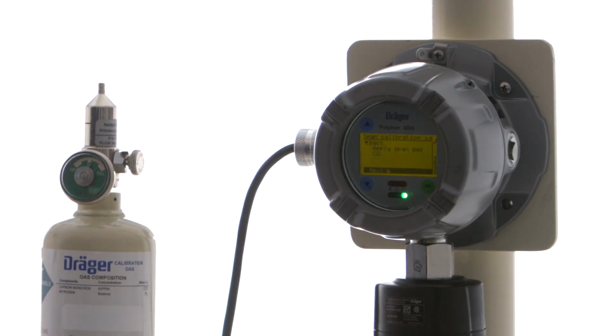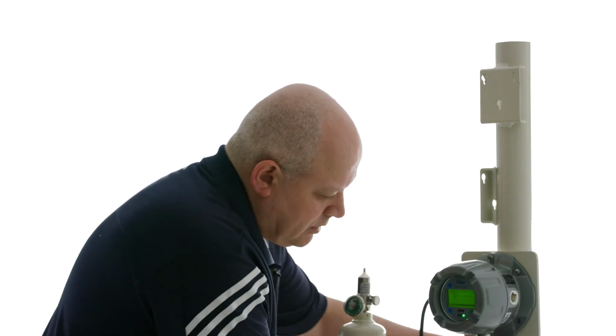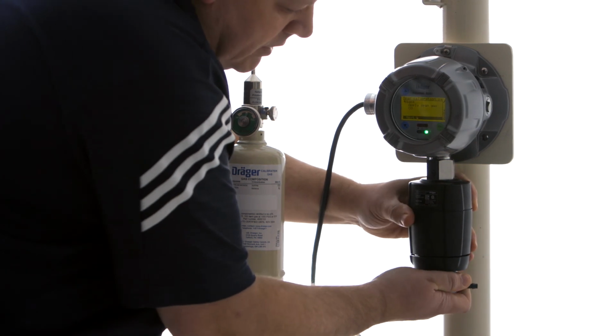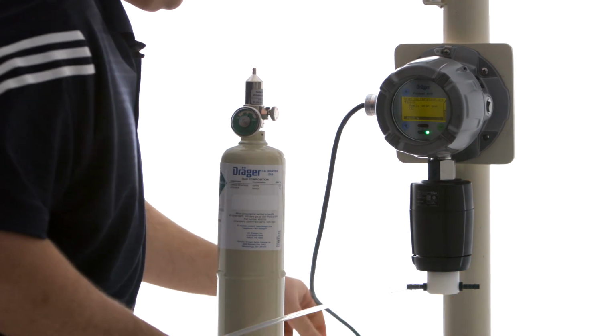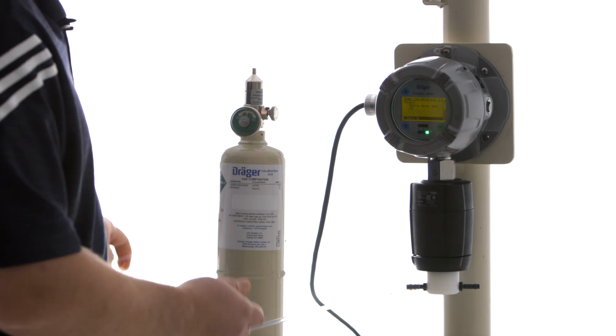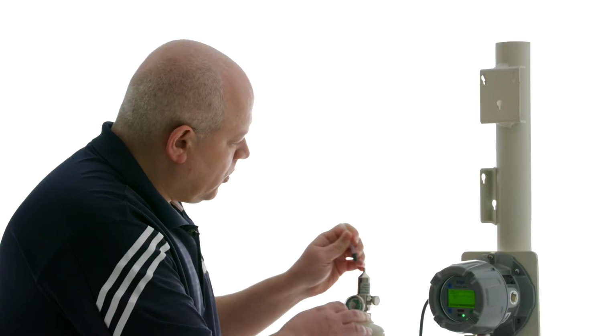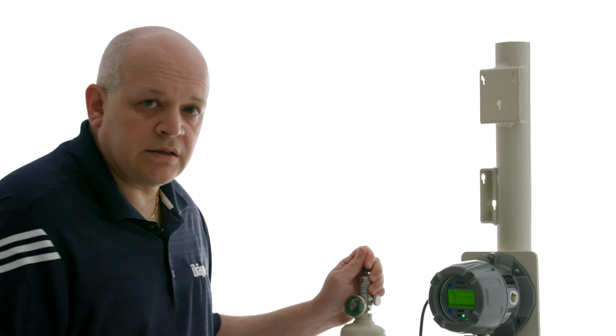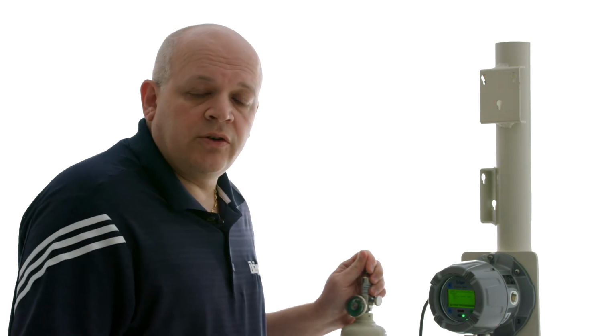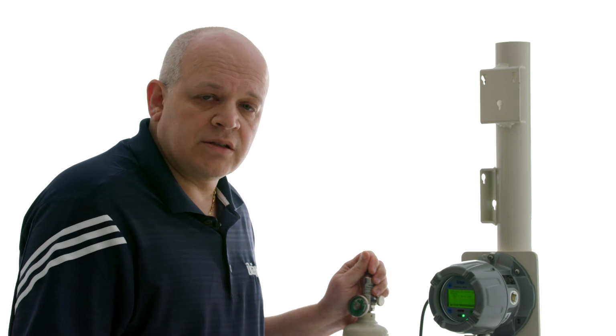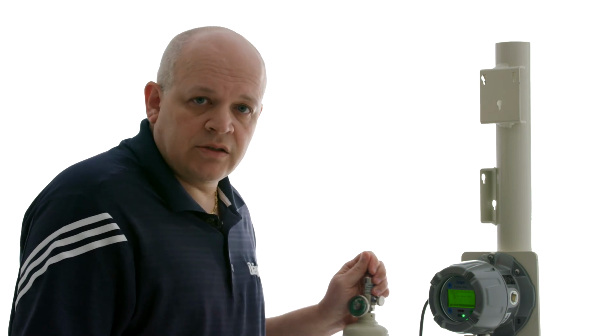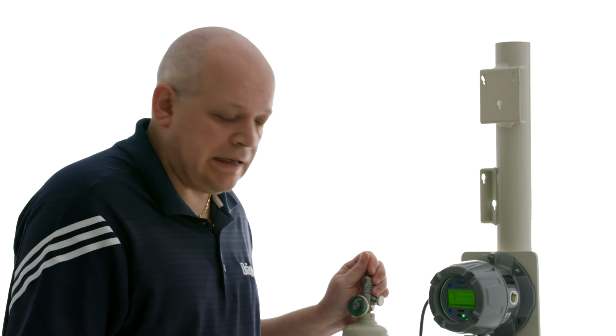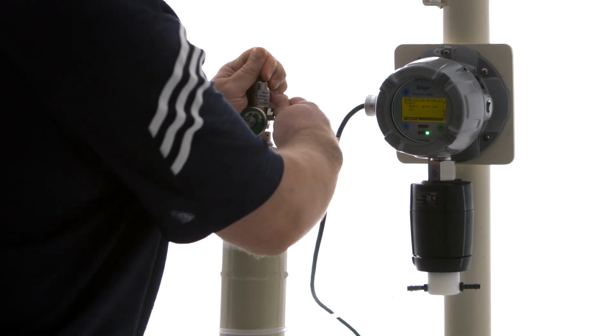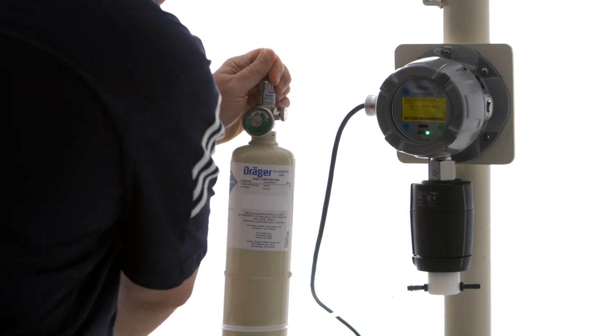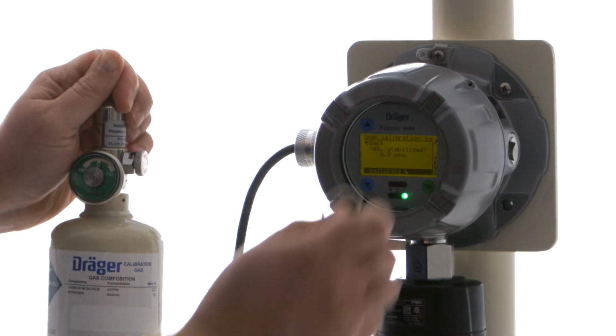So now it's telling us to apply the carbon monoxide gas. So we're going to put our calibration adapter or calibration cup onto the sensor. It's just a friction fit. If you notice, I'm using a really long tube for calibration. Ordinarily, we recommend using a tube that's as short as possible, especially if you're doing a reactive gas calibration such as ammonia or chlorine. And in those cases, you're going to use our reactive calibration kit. So we're going to turn on our gas. We're going to say next.